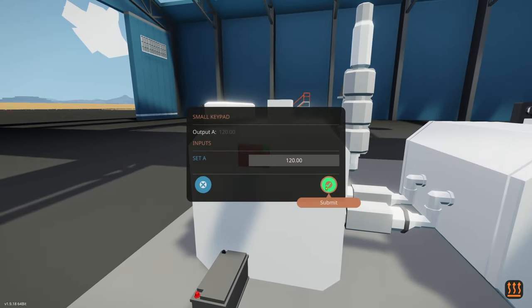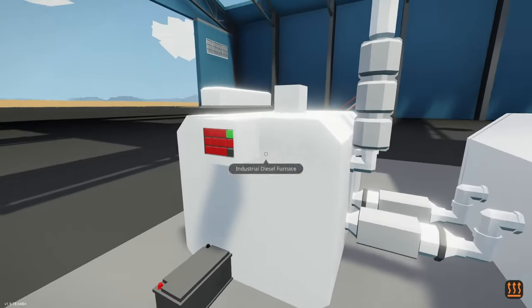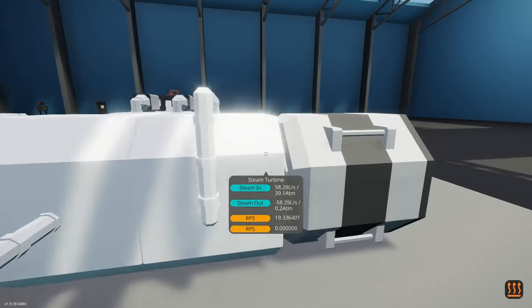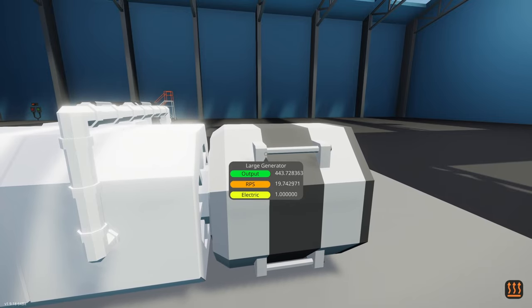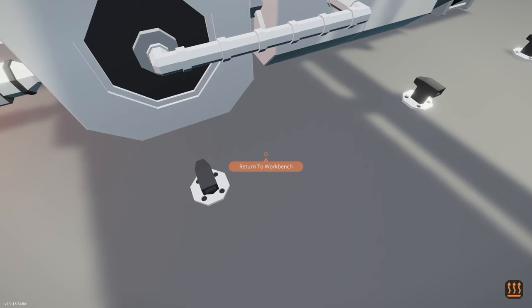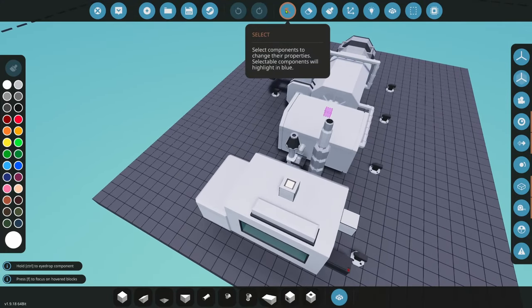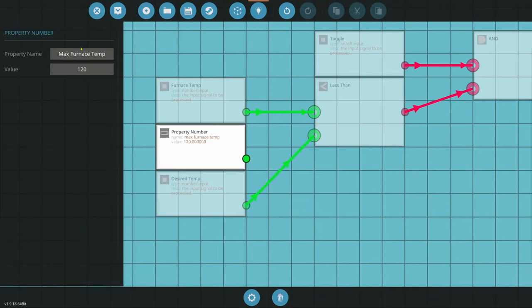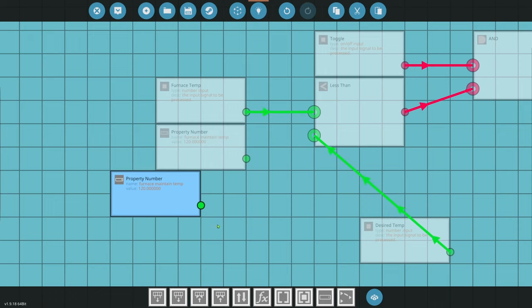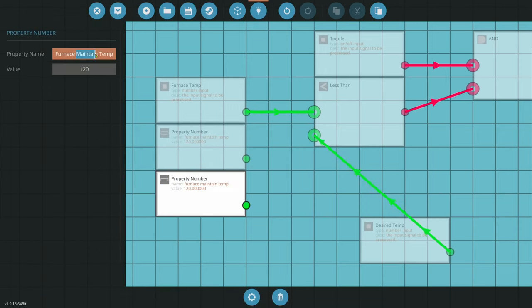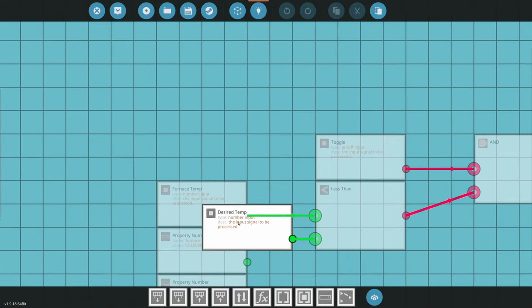What we're going to do now is add a little condition. We know that 120 is fine to sustain. So we'll add 'furnace maintain temp' — that's going to be at 120. We'll grab another property number — this is going to be 'furnace start temp', and we did 200. Let's do 200 again — that will be a little bit quicker. We don't need desired temp anymore — that was for our keypad. If you want keypad control you can, but what we're going to do is use a numerical switch box in here. So: furnace maintenance temperature is going to be our off value, and furnace start temperature is the on value. We're going to start our furnace at a hotter temperature so that things get going more quickly.